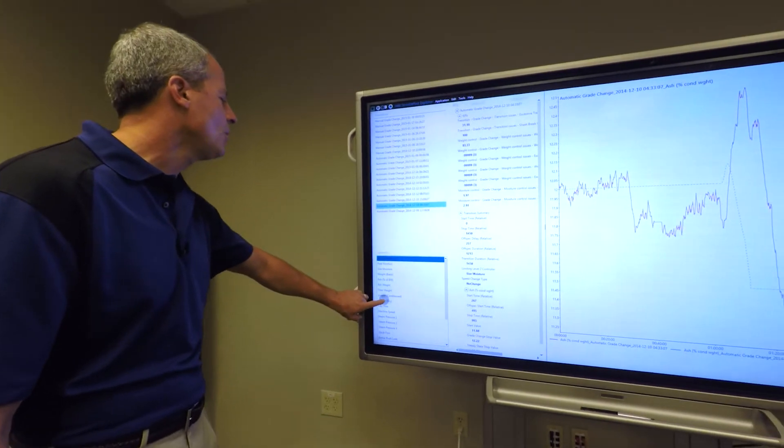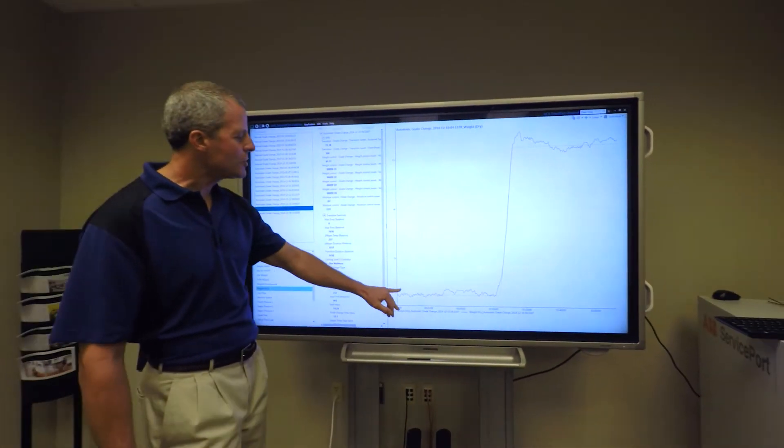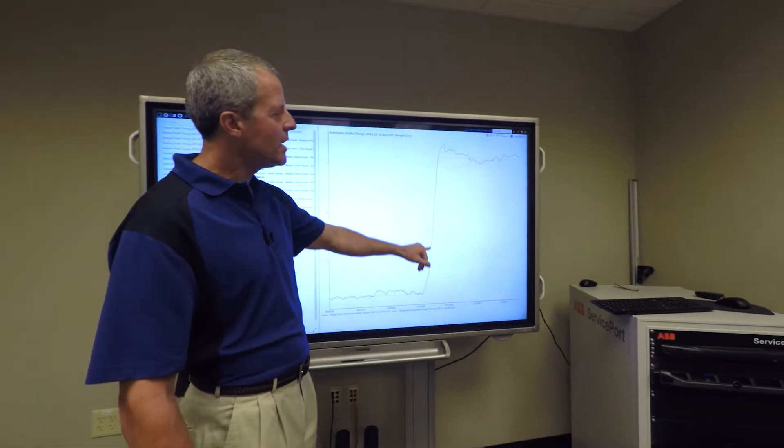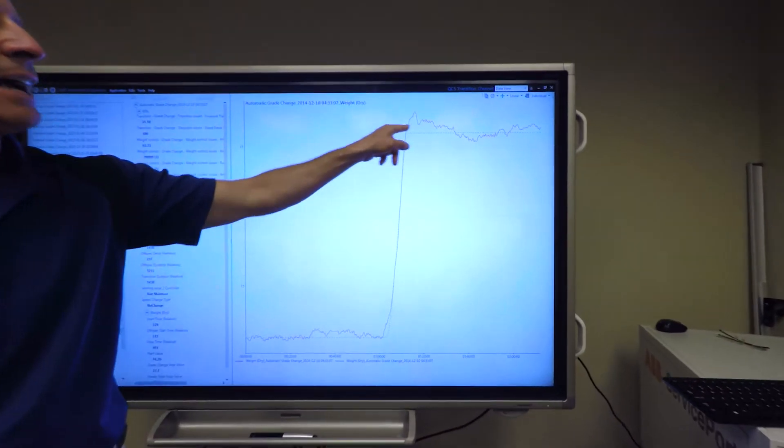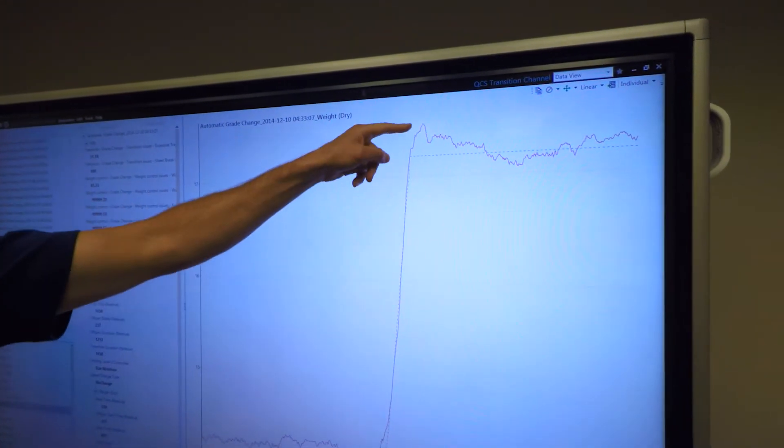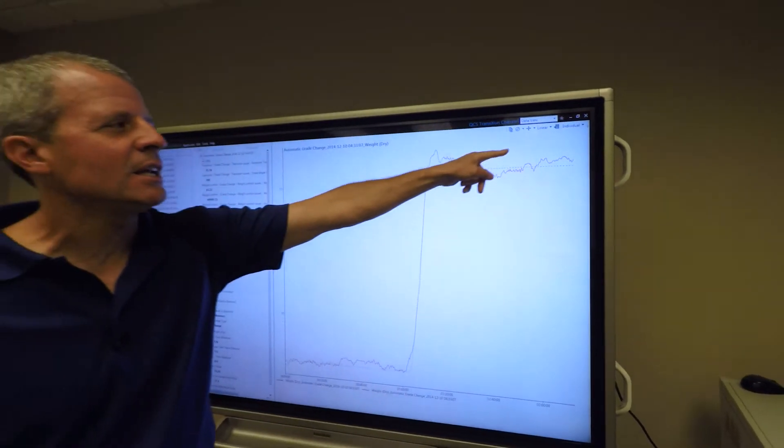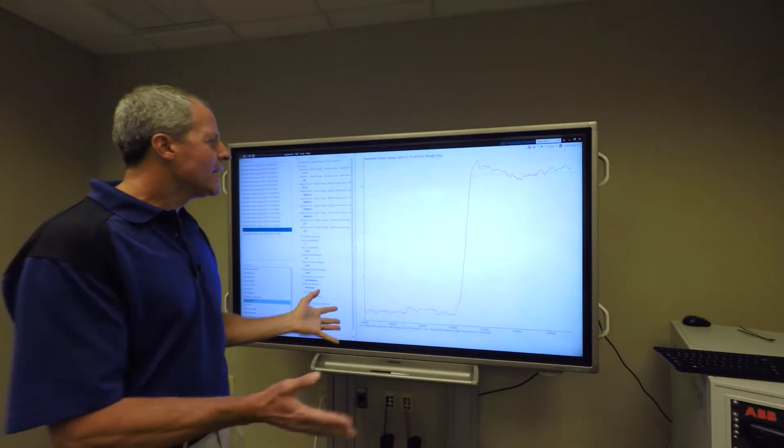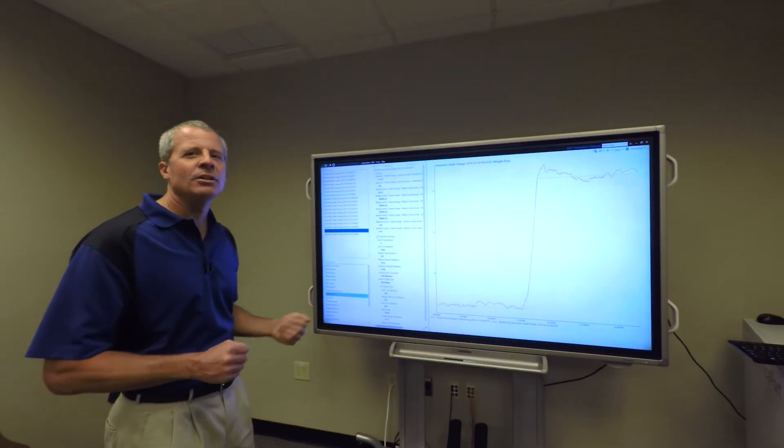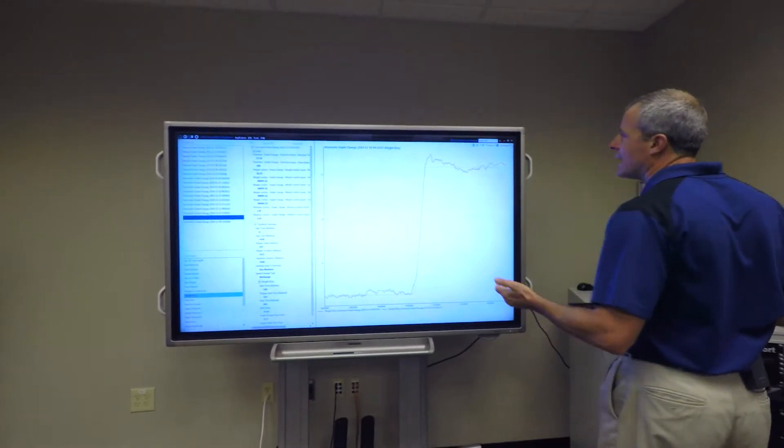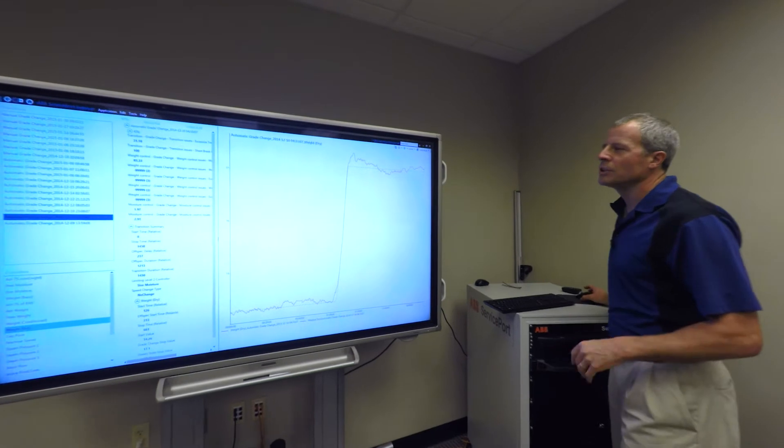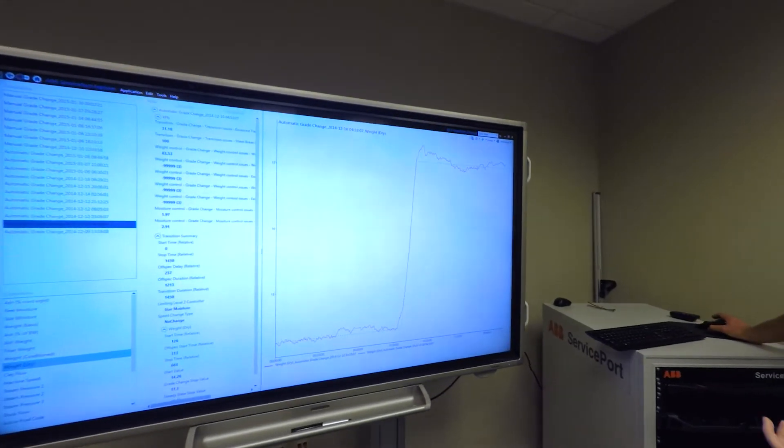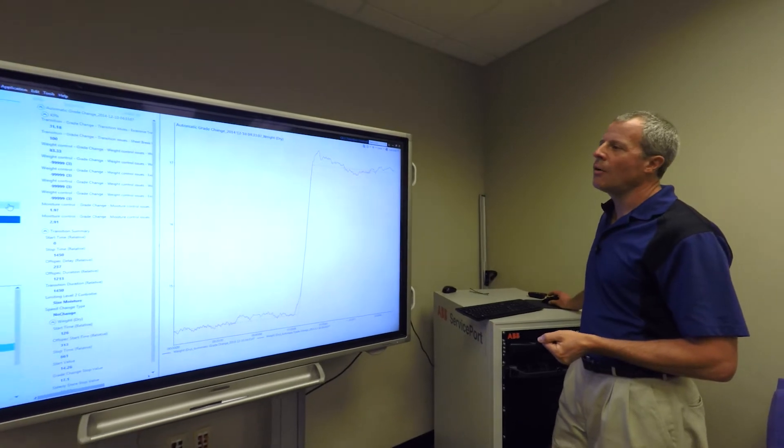If we grab the dry weight, we can see the dry weight measurement. This is before the transition, and then here we have the transition itself. The dash line shows you the target, and you can actually see the deviation of the measurement from the target as we're settling into our new grade. That's data that we have. We can look at that on our historical trends or on the DCS system. But the additional offering with the QCS transition channel is in addition to looking visually at this data, we can compare transitions.